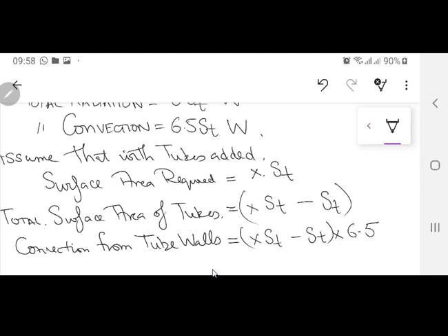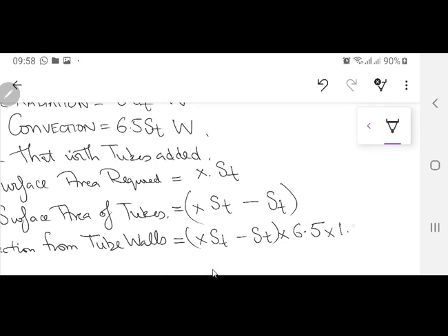And in this book they have given a factor that when you have tubes with oil flowing through them, because of the oil falling down, it is going to have a siphoning action and the convection rate is going to be increased by approximately 35%. What I mean by that, convection was happening inside the tank too, it was radiating the heat. With tubes, the oil is going to fall down from the top, come down to the bottom.